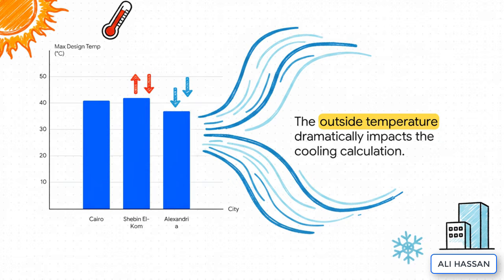And this right here is a perfect example of why location is everything. The hotter it is outside, the harder that heat is pushing to get inside. So if you're designing a cold storage room in Cairo, you've got to plan for 41 degrees Celsius heat. But if you're in Alexandria, it's 37 degrees. That 4-degree difference might not sound like much, but it has a huge impact on the final power calculation.